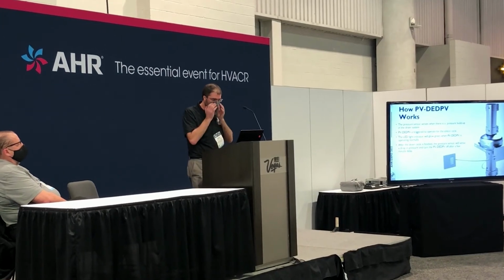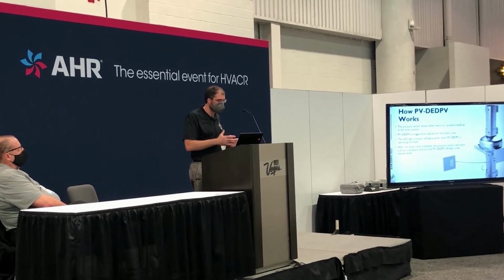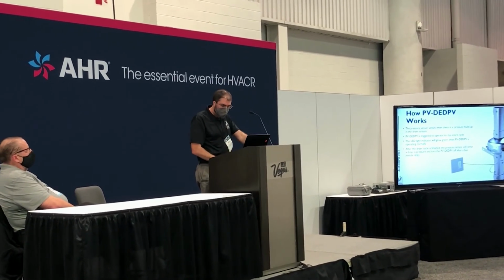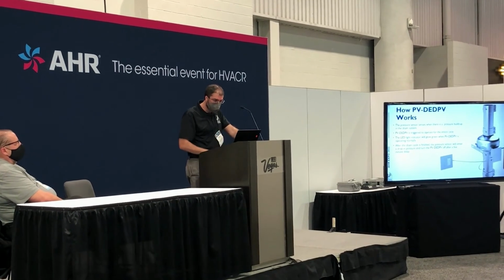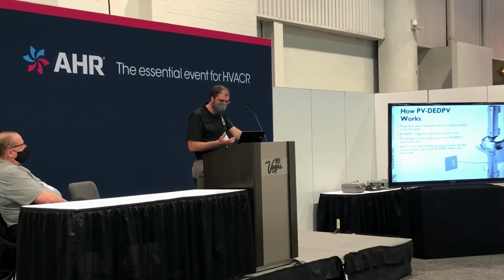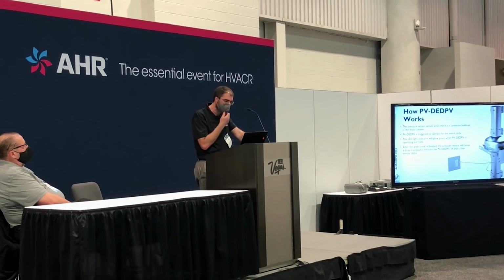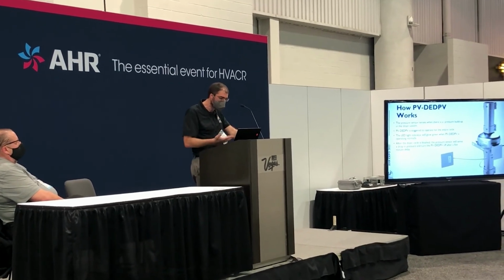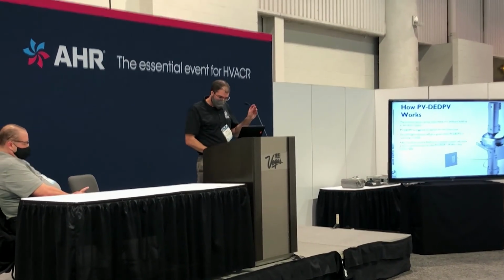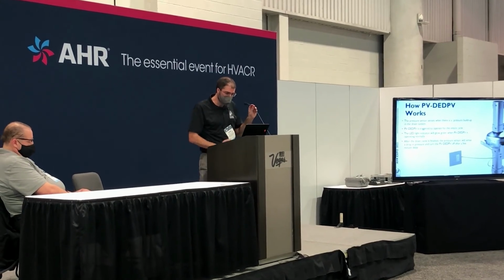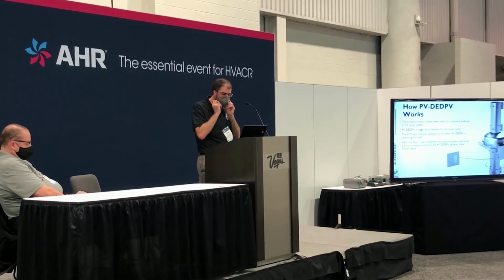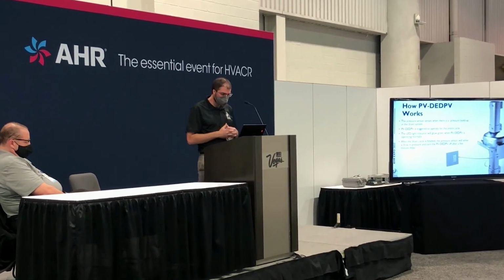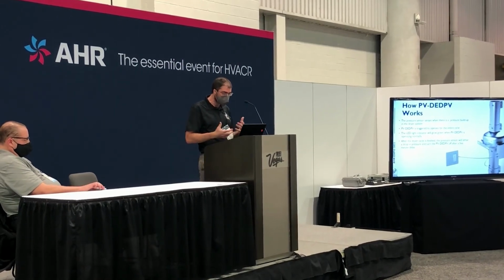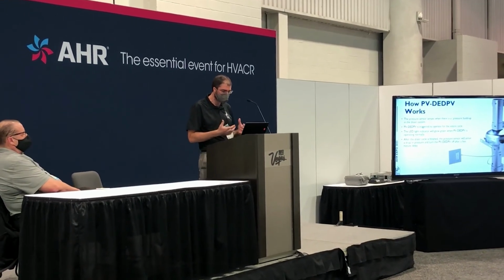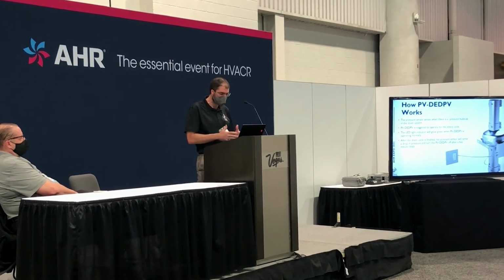And then we need to talk about the proximity of the fan to the dryer. It's of critical importance. The DEDPV should not be installed less than 5 feet or more than 40 feet from the dryer outlet. The maximum distance criteria is to help ensure the DEDPV will acutely respond to dryer fires by shutting off prior to moving the flames further downstream inside the duct.